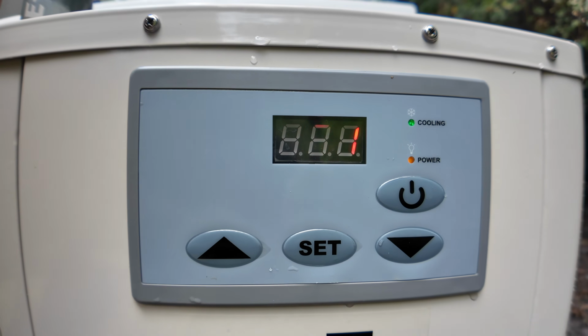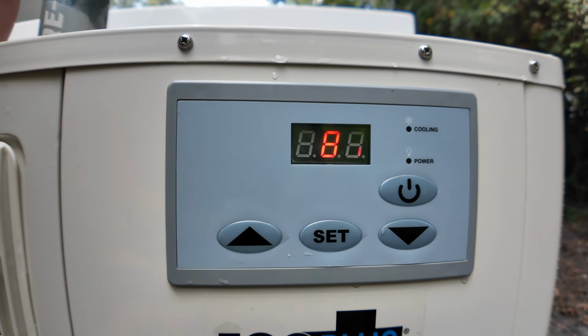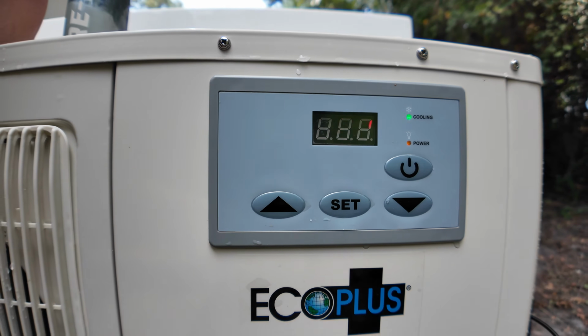I also wanted to mention their chiller choice. By using a 1/2 horsepower Eco Plus chiller, that's only gonna pull around 7 amps, which isn't that much, and only when the chiller is working hard. If you upgrade to the 1 horsepower Eco Plus chiller, that's gonna pull somewhere around 10 amps, which isn't that much more, and again that only happens when the chiller is on and chilling down the water. But because of the insulation and the lid, it doesn't necessarily have to do that 24/7.